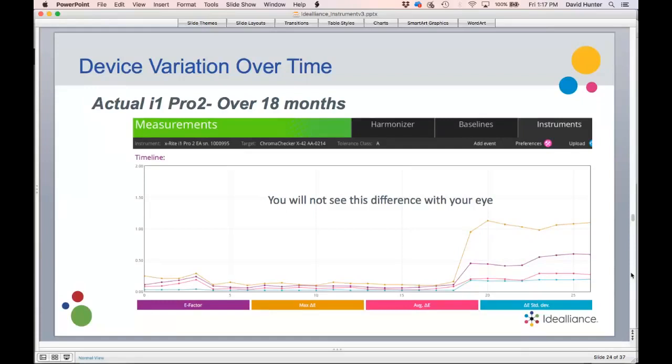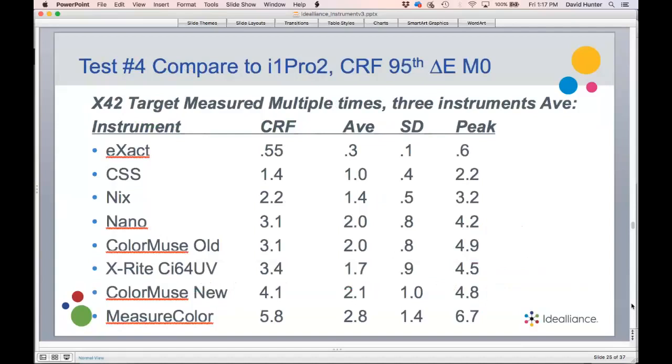If you move to a more proactive assessment model of running your color department, using a tool like this to check your instrument once a week or once a month, you know when that instrument goes out, and so you know when it needs service. And if it doesn't go out, you don't need to send it in because it is precise to what it's supposed to be. So it's a change of mindset in terms of making this work.